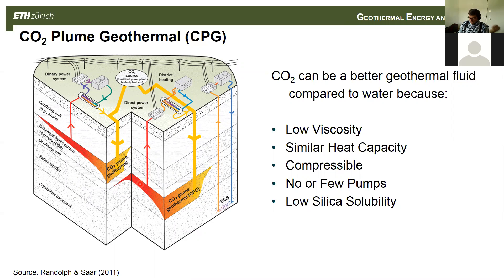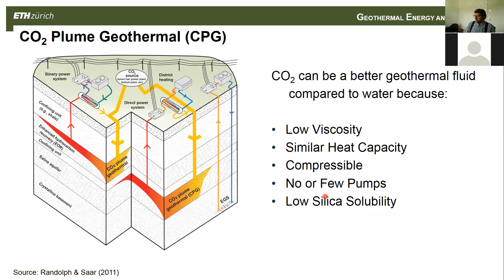CO2 is also compressible, which just means the density changes. Water is incompressible because we assume the density is constant. Because the density of CO2 changes, you get this thermosiphon effect, which reduces your need for pumps. CO2 is also different from water because its solubility is different — salts that can dissolve into water just don't dissolve into CO2. So you don't carry those salts up to the surface. CO2 has its own set of problems, but it offers some relief in that department.